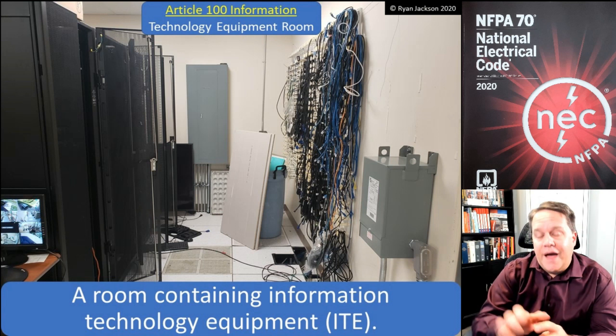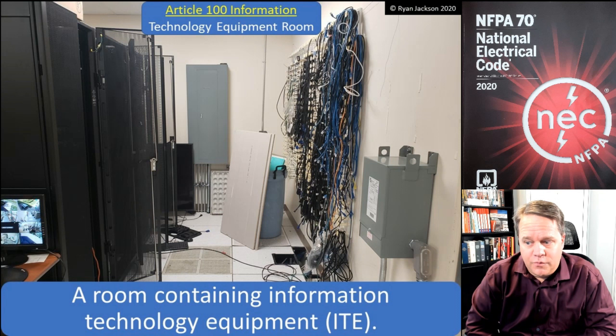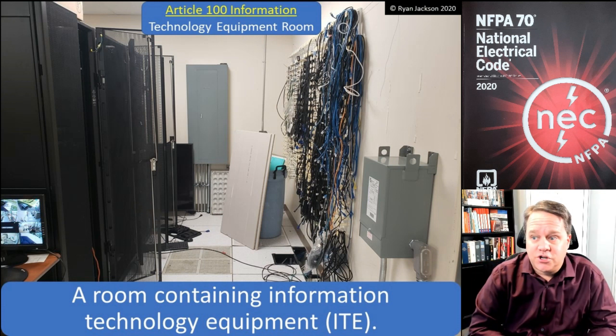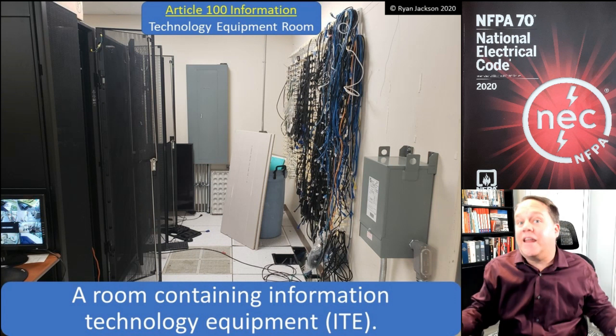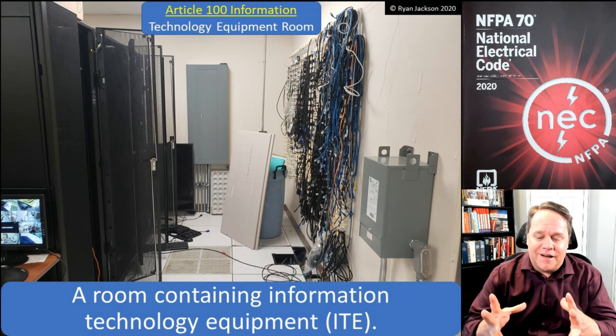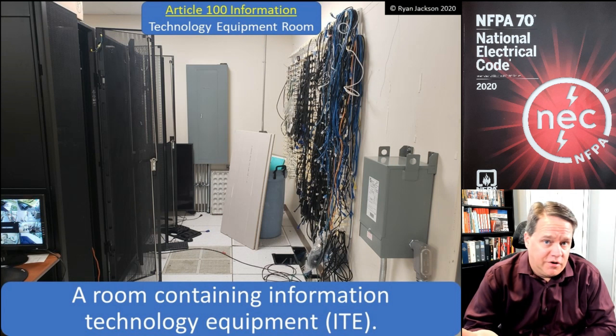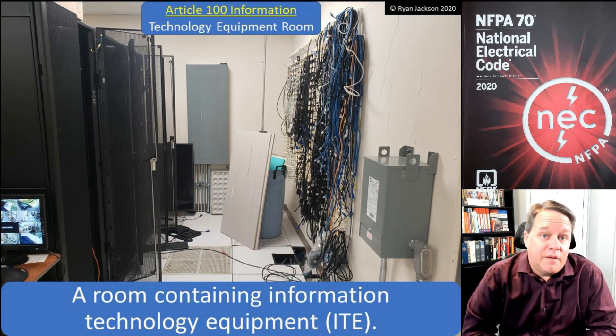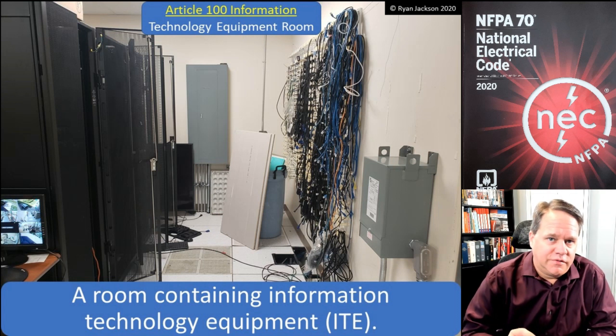You had to have a disconnect that shut off everything in that room. In earlier versions of the code it had to be located near the door, had to be a push button, and pushing it had to shut off everything in the room. That's a lot of baggage — what if someone accidentally bumps that switch and you lose all the computers for a data center? So a lot of people didn't want to comply with Article 645. You didn't have to — as long as you used plenum rated cables.